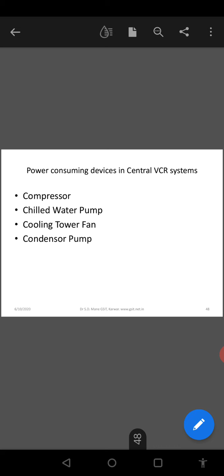What are the main power consuming devices in a central vapor compression refrigeration system? There is the compressor, that is the chiller, then the cooling water pump, the cooling tower fan and the condenser pumps. I think we also studied the effect of variation in evaporator temperature on compressor power consumption. The compressor is the major unit which consumes power in an HVAC system, so the evaporator temperature basically decides the power consumption.